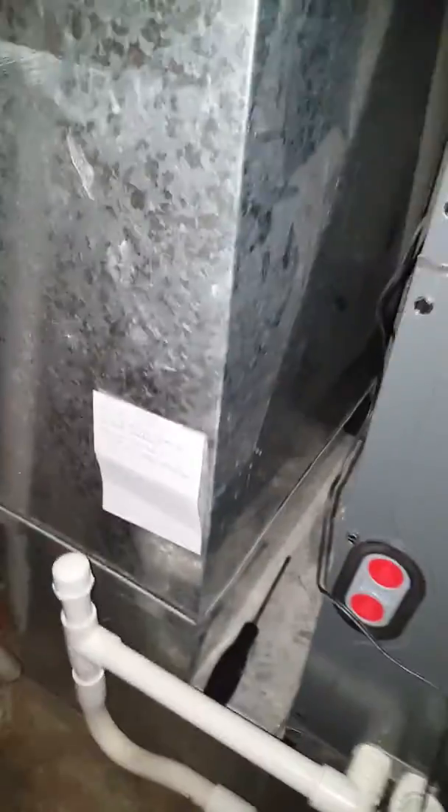Very good duct system. There's a 60-amp breaker on the unit here with the electric line coming in, and a shutoff switch on the overflow drain. It's got a clean-out and goes down through the slab for drainage, which goes over to a floor drain, and that's all sealed nicely.